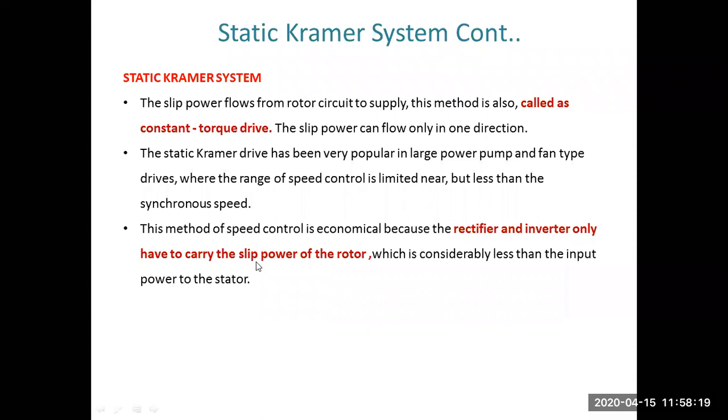Now this method of speed control is very economical because the rectifier and the inverter only have to carry the slip power of the rotor. What does it mean? The rectifier and inverter only have to carry slip power. What is slip power? We know that it is the power which is wasted on the rotor side, in the external resistance connected for the starting purpose of the motor.